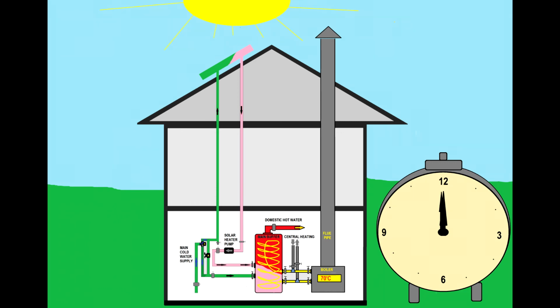Can you imagine? It will depend on the size of the solar heater panels, how many you have, and how much they are capable of heating the water, because this is all based on a ratio. You have to see the temperature that goes into these solar heater panels and the temperature which comes out. If you have an energy storage device, you can use a smaller heater panel, because you will progressively store the energy. But for instant heating you need a much larger panel, because you need more instant energy. This will be the only way for you to design the system.